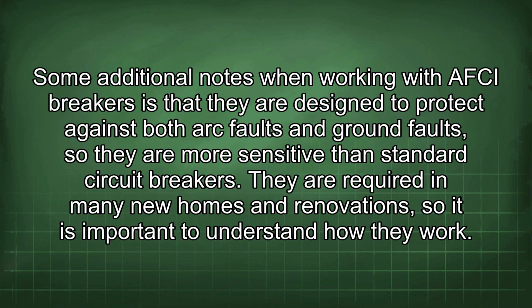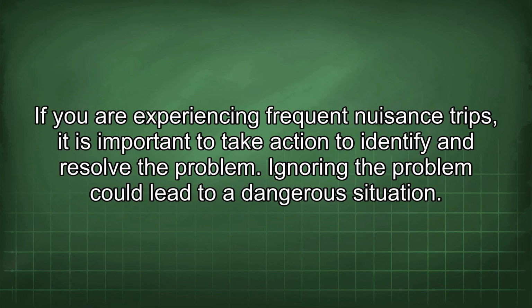Some additional notes when working with AFCI breakers is that they are designed to protect against both arc faults and ground faults, so they are more sensitive than standard circuit breakers. They are required in many new homes and renovations, so it is important to understand how they work. If you are experiencing frequent nuisance trips, it is important to take action to identify and resolve the problem. Ignoring the problem could lead to a dangerous situation.